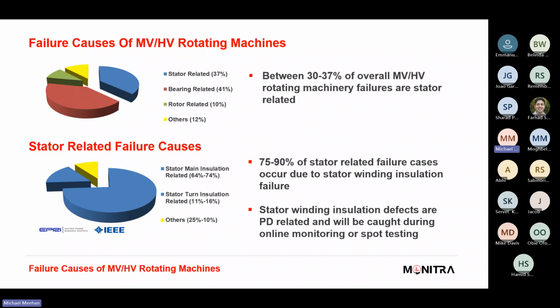But when you want to actually see the condition to make those business cases, you might have a requirement where the outage, you can't make it next month as planned, or in the next 6 months, because of operational conditions you need to keep running. If you've got the ability to take some online measurements, you can be more confident that, yeah, we can push an outage out another 6 months, another 12 months, because we're not seeing anything that tells us otherwise. So it's all about getting that condition data, making it relevant and useful, so you can make these decisions with less of a finger in the air and hope that nothing fails when you make those decisions. So it's a risk awareness, risk reduction type approach.